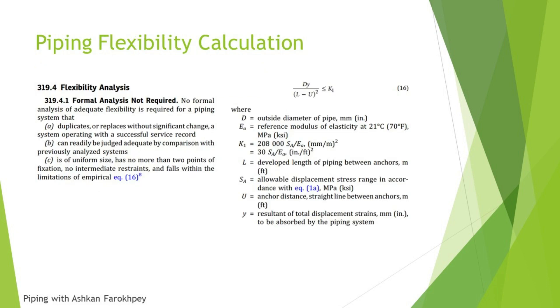In ASME B31.3, we have a flexibility analysis part. In this section, we have to calculate the displacement that is added to our piping system from the thermal movements. By calculating that value, you have to compare it to the allowable stress range or allowable displacement stress range that our material has. In this section, the code says that when you duplicate or replace a system without significant change from another system that has had successful operation, you don't need to calculate the flexibility analysis.